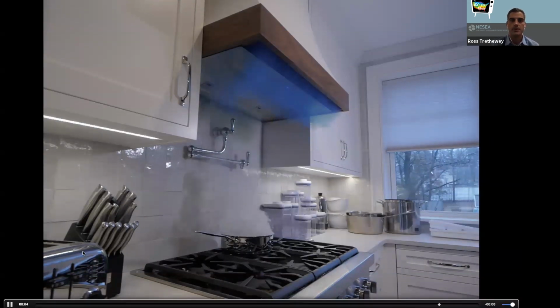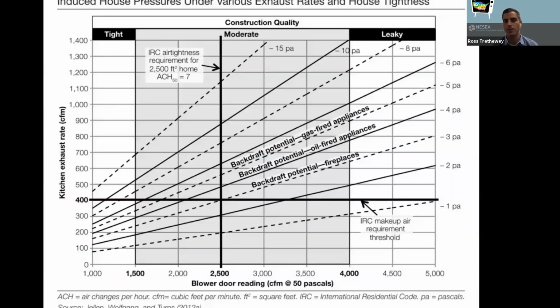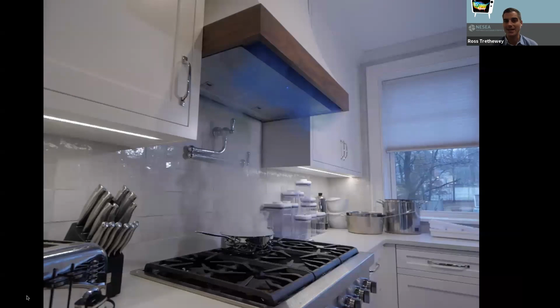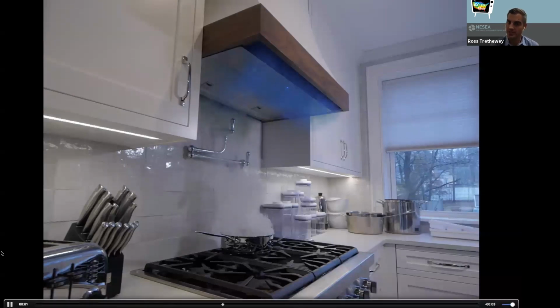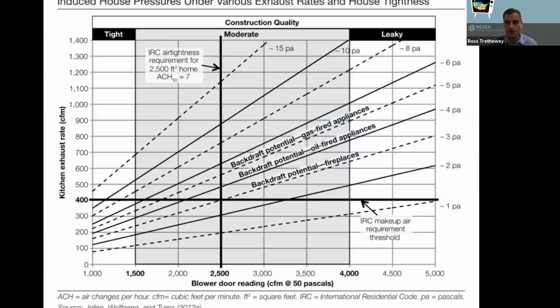The only thing I'll mention here is that this type of solution may not be the best fit in a really tight building. So we have to be sensitive about the air tightness of the building. Also, the closer you bring the makeup air to the cooking surface, the higher the risk is for spillage and not getting proper entrainment and proper capture of the contaminants. So when it's done right, well executed, it's a great way to go.